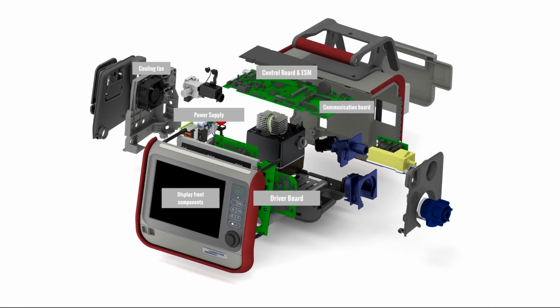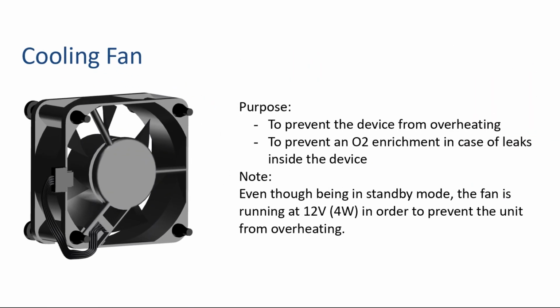We will now move to the cooling fan. The cooling fan has 2 purposes. The first is to prevent the device from overheating, and the second is to prevent oxygen enrichment in case of leaks inside the device. Note that even when the unit is in standby mode, the fan runs in order to prevent the unit from overheating. The fan blows into the device. It is controlled by a temperature sensor, also called an NTC resistor, which is located on the driver board.